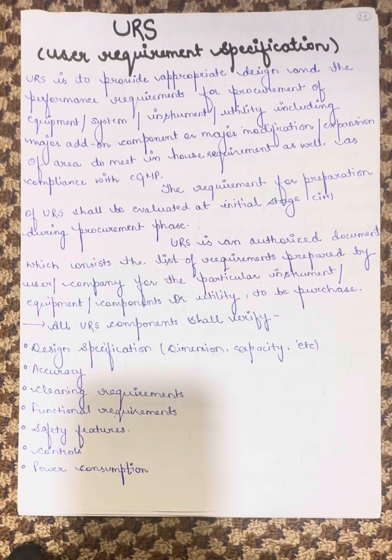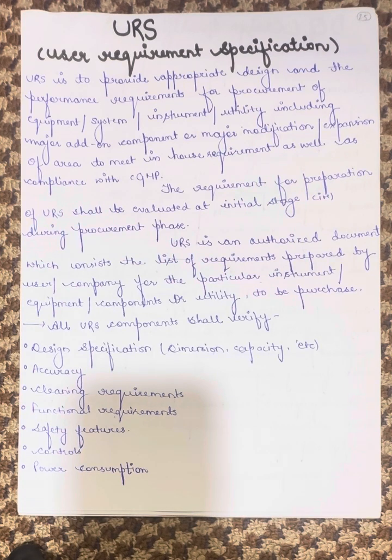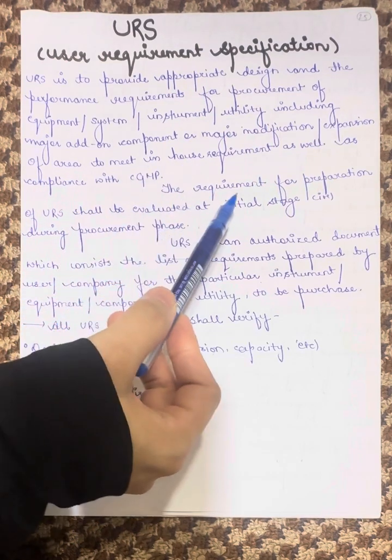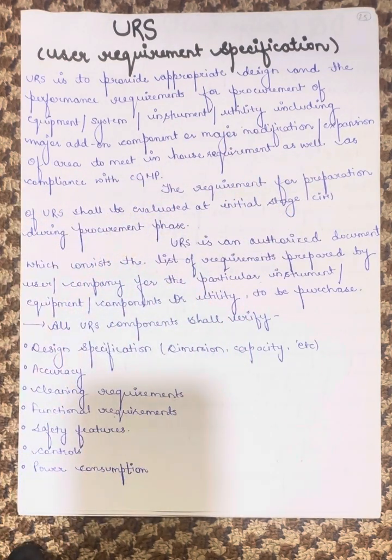URS stands for the User Requirement Specification. URS is to provide appropriate design and the performance requirement for the procurement of equipment, system, instrument or the utility including major add-on components or major modification or expansion of area to meet in-house requirements as well as compliance with the CGMP, current good manufacturing practices. The requirement for preparation of URS shall be evaluated at initial stage, that is during the procurement phase. URS is an authorized document which consists the list of requirements prepared by the user or a company for the particular instrument or equipment or the components or the utility to be purchased.